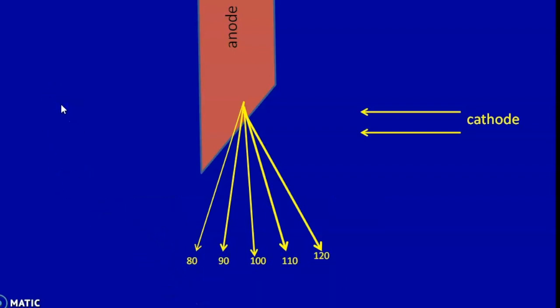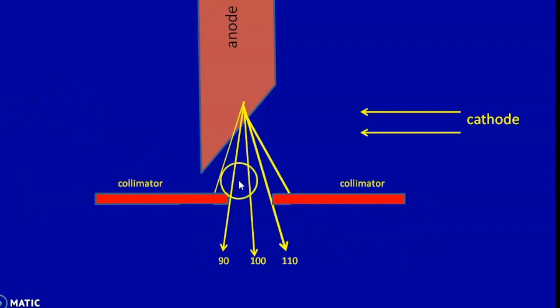Also, we can reduce the severity of this effect and make it less pronounced in three ways. The first is with the help of collimators. These are like our window curtain blinds that restrict the size of the primary beam projected towards the patient. Lesser field size means the extreme values or the ranges of the X-ray beams on either ends are cut off and the beam is made less divergent and the central field is allowed to be focused on the patient.